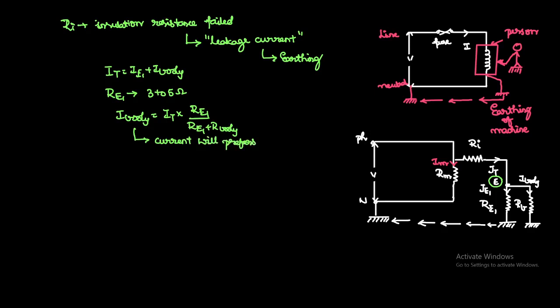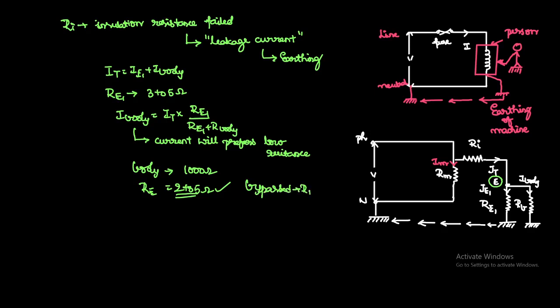We provide Re of 3 to 5 ohms. Current prefers the low resistance path. The body resistance in worst condition can be thousands of ohms, while earth resistance is only 2 to 5 ohms. So current prefers the earth resistance path — the entire current is bypassed through Re, and only a very small amount flows through the body. That is the purpose of earthing.